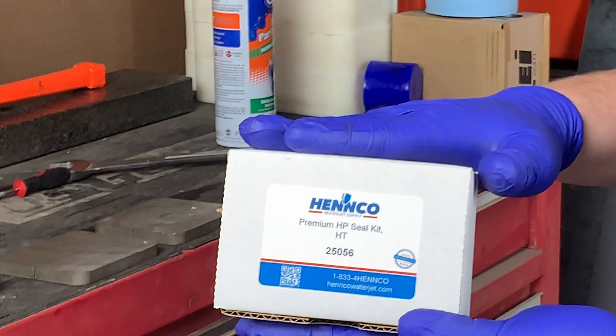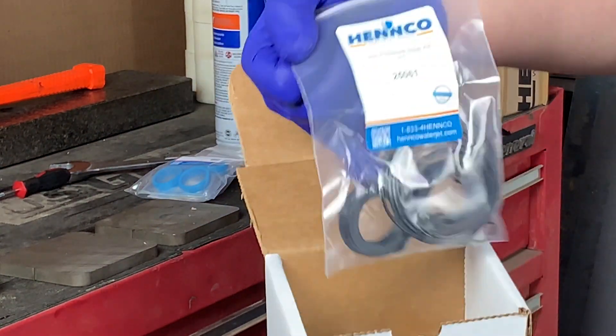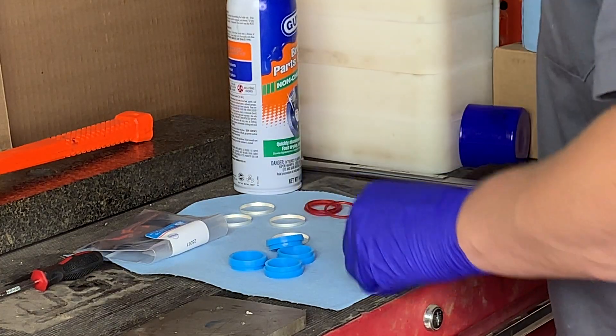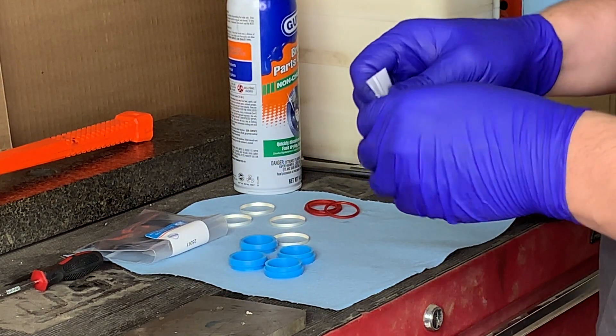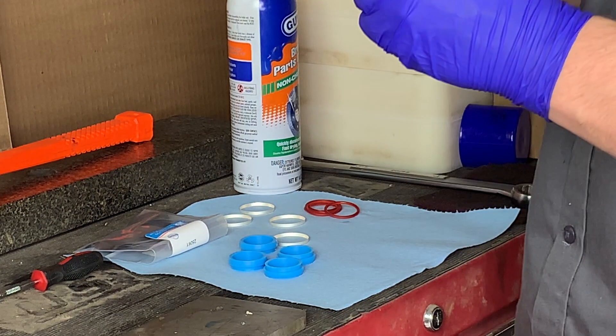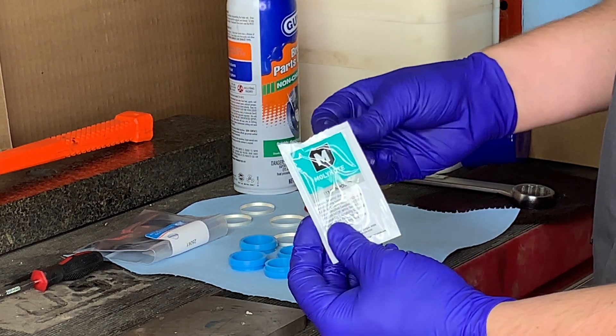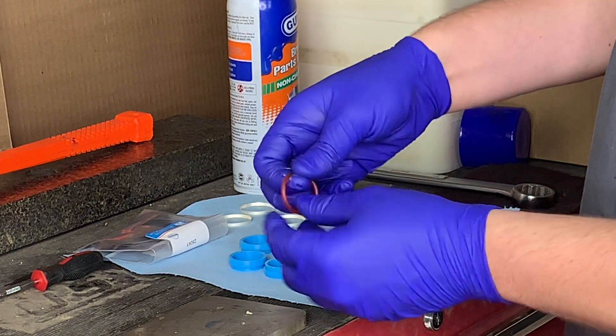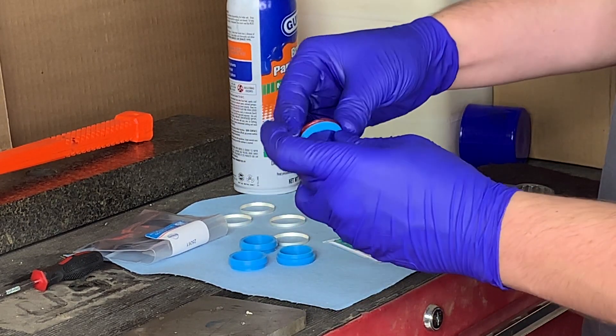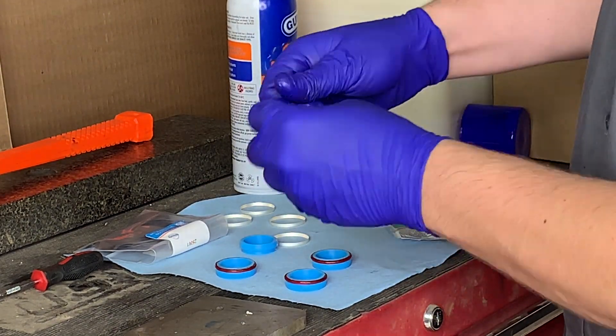Alright, we're ready to go ahead and put in some new parts. From Hennco you're going to want to use part number 25056, which is our premium seal kit. In that seal kit you're going to get a set of high-pressure seals which includes four seals, four hoops, four O-rings, as well as a little packet of grease, bronze backups, and all the low-pressure seals needed to do a high-pressure seal change. We're going to go ahead and take a little bit of that high vacuum grease with a clean set of gloves and lubricate our O-rings, making sure that we coat each and every piece of the O-ring. Once the O-ring is fully coated, go ahead and place that O-ring on the high-pressure seal as shown here.